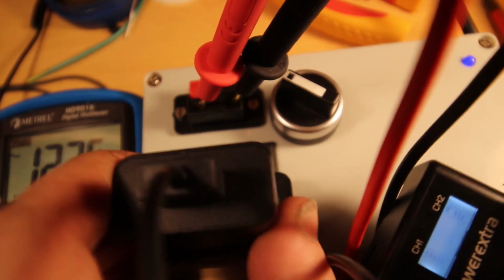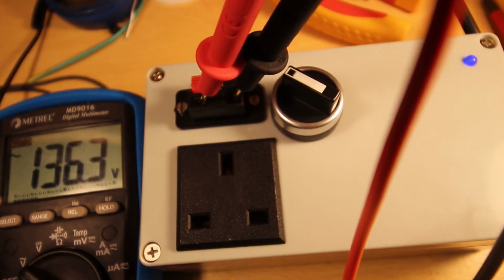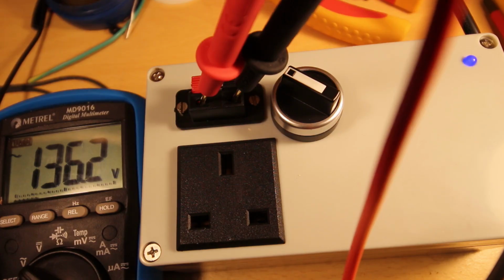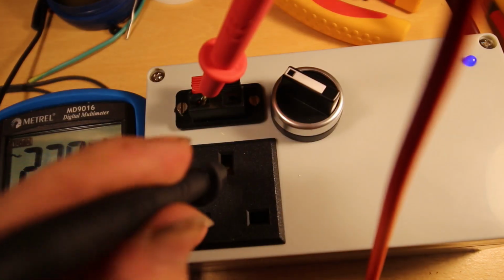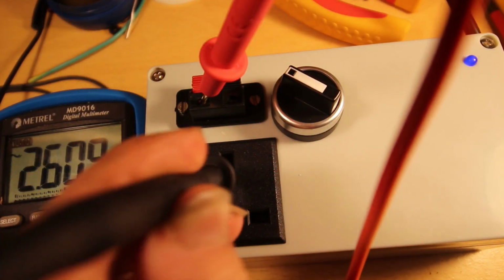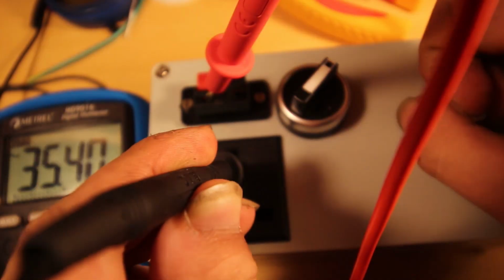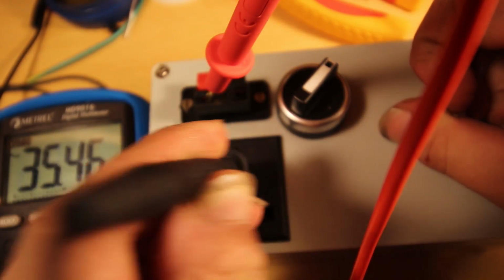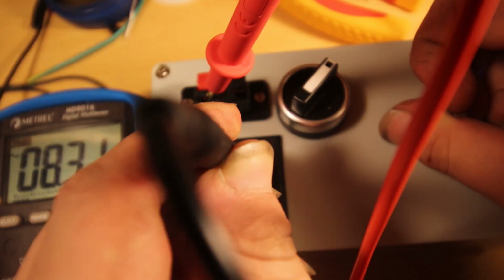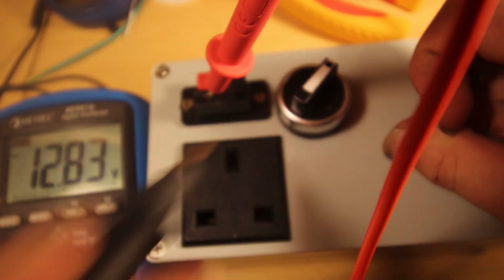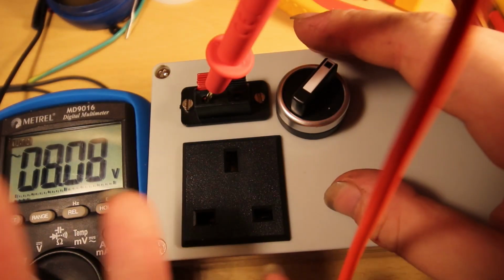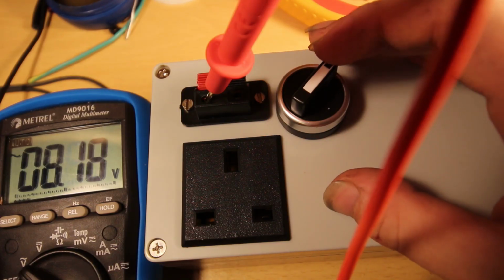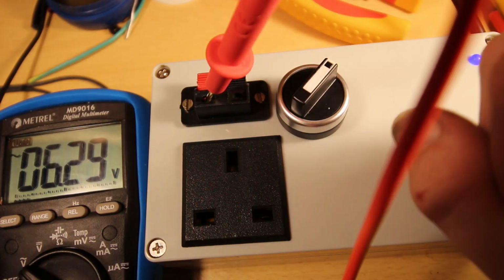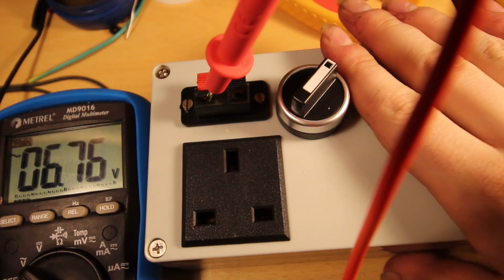The other thing I'll show you quickly - if I unplug this and take my meter probe out and stick it onto earth, there's a negligible voltage, and if I change it, there's 8 volts, again minimal. It'll jump around all over the place because they're not referenced. But it's not the full 240 volts, so it's not as dangerous as it might be. So yes, I'm happy with this - it's a useful little thing.